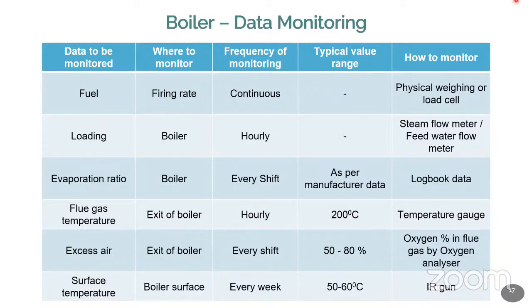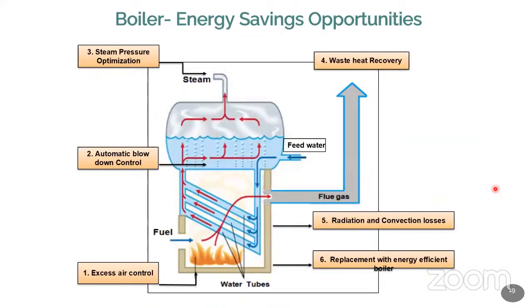These are all the instruments used for measuring the system. The surface temperature of all the boiler equipment can be measured by an IR gun or IR thermal imager. Now these are the areas where you can monitor the system and find energy saving possibilities. I told you we have excess air control with the help of an FD fan. The forced draft fan can be operated at variable speed. So an FD fan with a VFD drive will give the correct air combination to the fuel, so that can possibly save energy.